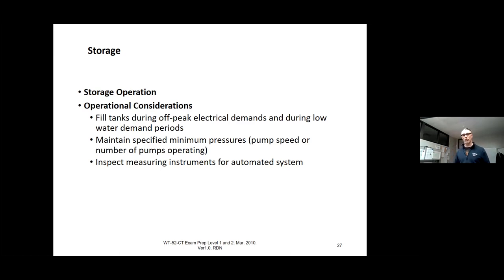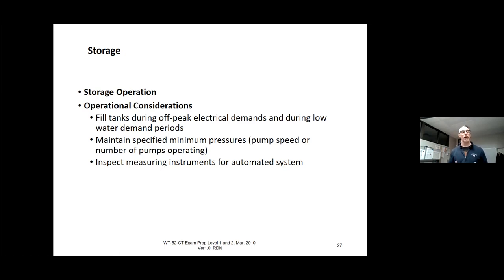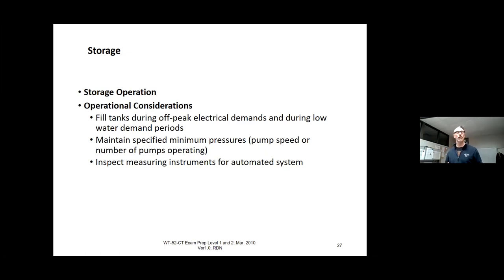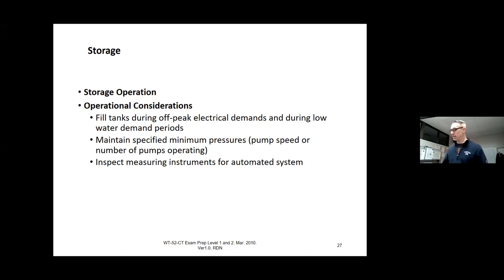You want to maintain specified minimum pressures all the time — it's not good to fluctuate pressures throughout your system. If the system is automated, always make sure your level and pressure transmitters are operating correctly; if they're not, it could cause a lot of issues. If you're using a level transmitter to turn a pump on and off, make sure it's calibrated and checked often and that your safeguards are in place. We send people out to inspect and make sure the float bulbs and transmitters are all working correctly.